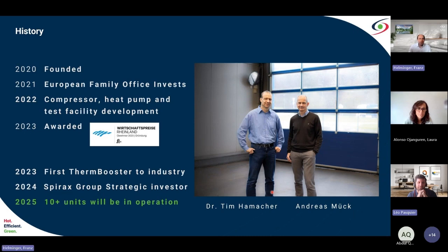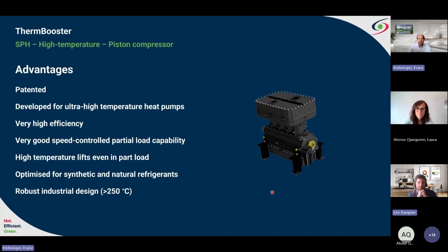To the core technology: we are producing a patented high temperature piston compressor, which was developed for ultra high temperature heat pumps with a very high efficiency, also in partial loads, with good speed control. High temperature heat pumps normally need a high temperature lift compared to other heat pumps, and the compressor is optimized for high temperatures and for the synthetic and natural refrigerants needed for them, in a robust industrial design for more than 250 degrees maximum in operation.